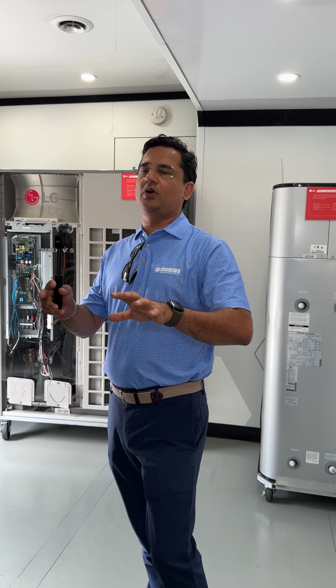So you have a 10-ton compressor right now. You have two 10-ton compressors, and they are individual circuits. So imagine you have 6 compressors in a 60-ton. You lose one, you still have 5 compressors working. So your N+1 or N and a half is taken care of here. So you have a redundancy in the system. Practically, the startup is really easy. You turn on the unit and tell it how much water you want and what temperature water you want. You have enough water running through the system.